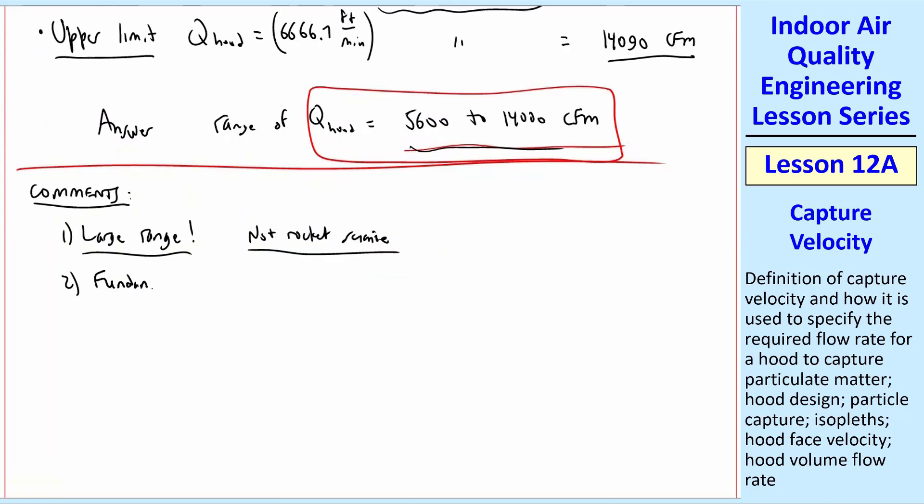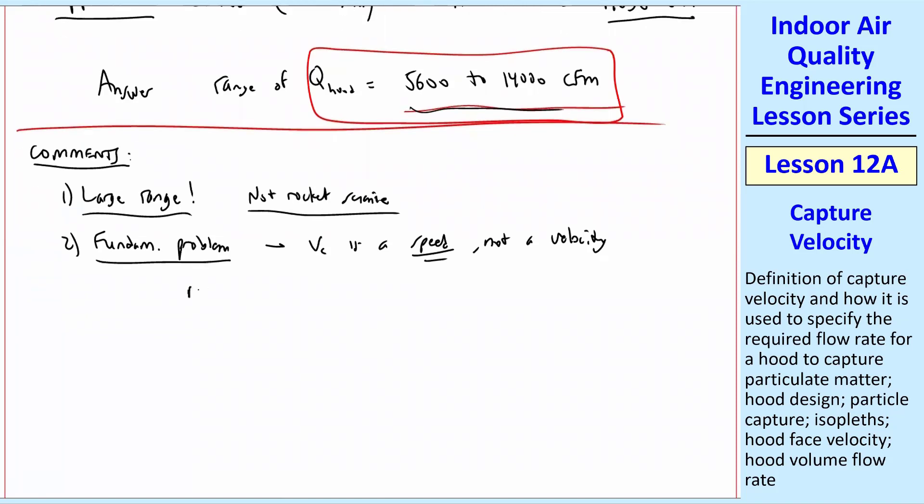Number two, there's a fundamental problem with capture velocity, namely that it's not really a velocity. VC is a speed, not a velocity. And I don't mean that the problem is just with the name. It's really not a good name. They should have called it capture speed. But it does not tell you anything about the direction, only the magnitude.